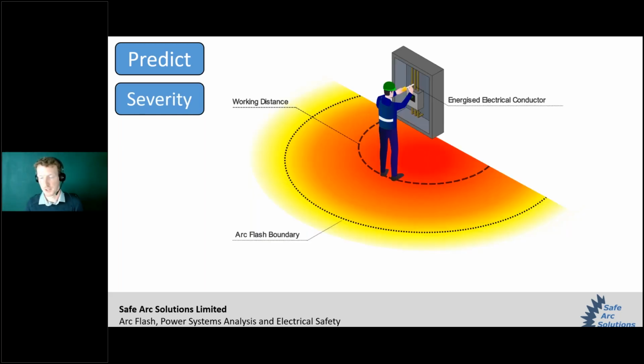Now, those two values I mentioned are important. The incident energy expresses the thermal energy at the worker's head and torso. So although your hand might be very close to where the arc happens, you actually calculate the incident energy and the severity of the arc a distance away, and that's because protecting the head and torso is the most important in terms of protecting vital organs.